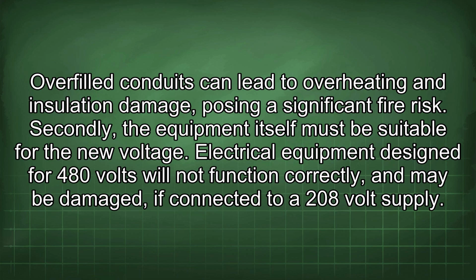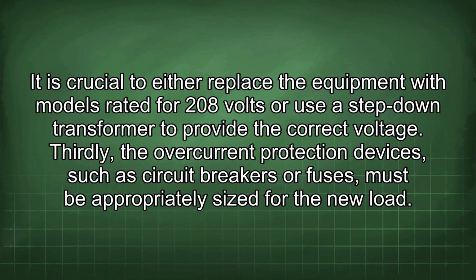Secondly, the equipment itself must be suitable for the new voltage. Electrical equipment designed for 480 volts will not function correctly and may be damaged if connected to a 208-volt supply. It is crucial to either replace the equipment with models rated for 208 volts or use a step-down transformer to provide the correct voltage.